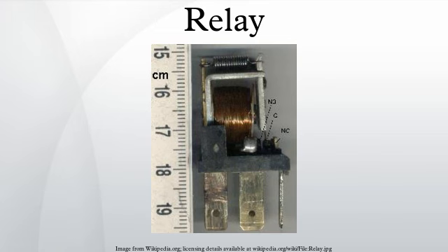A type of relay that can handle the high power required to directly control an electric motor or other loads is called a contactor. Solid-state relays control power circuits with no moving parts, instead using a semiconductor device to perform switching. Relays with calibrated operating characteristics and sometimes multiple operating coils are used to protect electrical circuits from overload or faults. In modern electric power systems, these functions are performed by digital instruments still called protective relays.